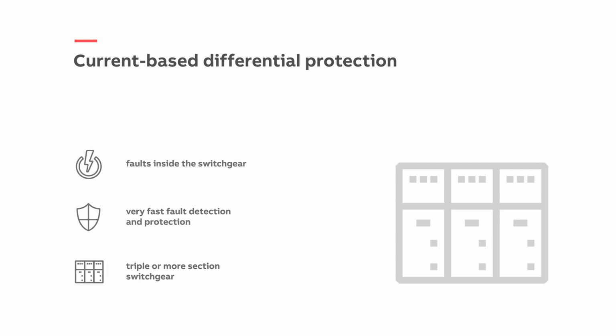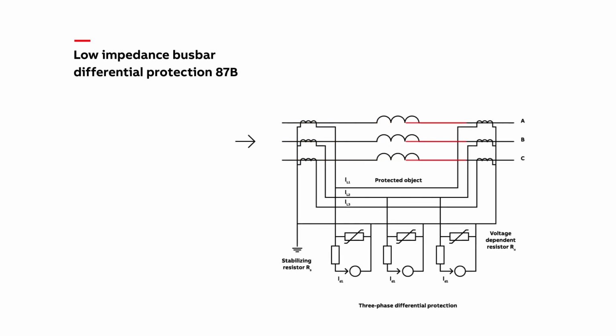Busbar differential protection works based on Kirchhoff's first law, also known as current law. Simply put, all the currents in the system, for instance in this diagram, which represents our switchgear, what current comes in must go out. If there is a difference, the protection relay sees the difference. This means that there is something occurring inside the switchgear, such as an arc flash, arc fault burning, or copper burning. This must be tripped immediately.